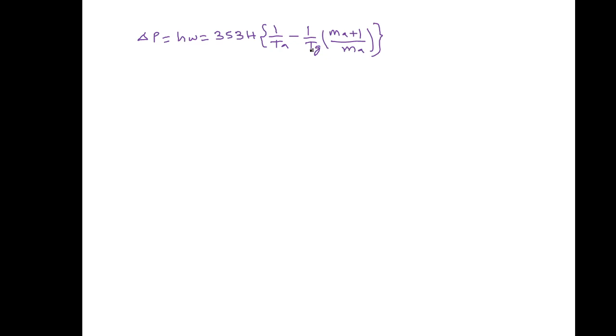So pressure difference delta P in terms of hot gas column is given by this equation number 13. Now after that, we know delta P is equal to HW in terms of water column, which is equal to 353 H in bracket 1 divided by Ta minus 1 divided by Tg, bracket Ma plus 1 divided by Ma, close this bracket. This HW is again written like this as 353 H divided by Ta in bracket 1 minus Ta divided by Tg in bracket Ma plus 1 divided by Ma, close this bracket.